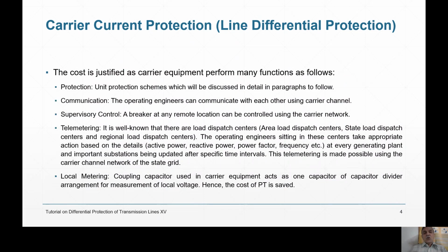So how can you justify the cost? To justify a cost just for protection is not good. But fortunately, this carrier current equipment does many functions. One, obviously, protection, and it gives a very good unit protection scheme. Another important function is communication. You can talk with another substation, another power station using the carrier system. You do not need BSNL people. You are talking to each other in power stations free of cost. Substations, power stations, you can talk free of cost.